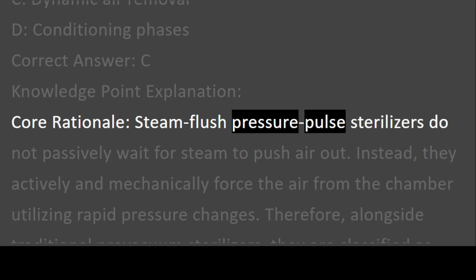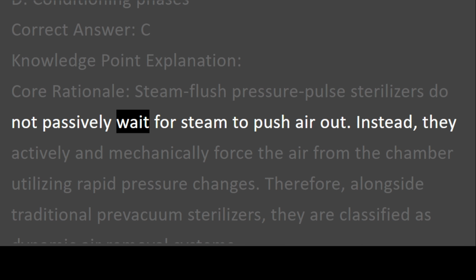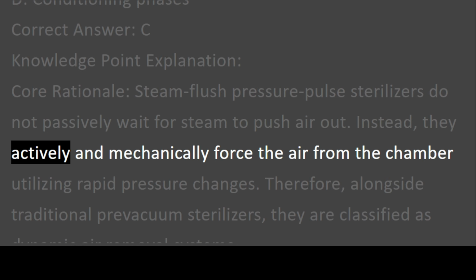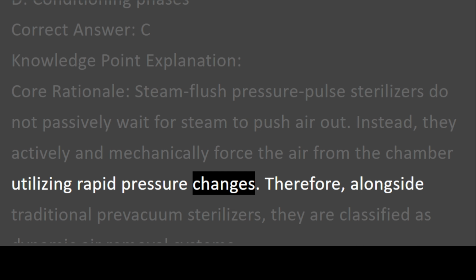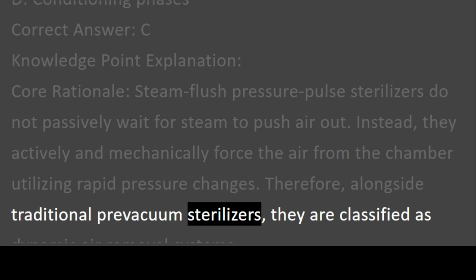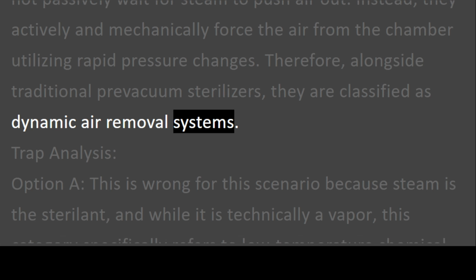Steam flush pressure pulse sterilizers do not passively wait for steam to push air out. Instead, they actively and mechanically force the air from the chamber utilizing rapid pressure changes. Therefore, alongside traditional pre-vacuum sterilizers, they are classified as dynamic air removal systems.